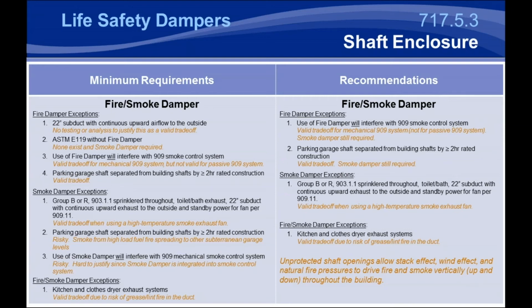Now this is when we first start getting into the different types of exceptions based on fire damper, smoke damper, and construction and use. So, of course, the ASTM E119 exceptions are there for fire dampers, but we get into somewhat of a legacy exception where you've got a 22-inch subduct and continuous upward airflow to the outside. This is basically kind of a legacy exception. It's been in the code for quite some time, but there's no testing or any work that's been done to justify this as a valid trade-off for protecting exposure from fire or allowing fire to get into that shaft and spread through the building.